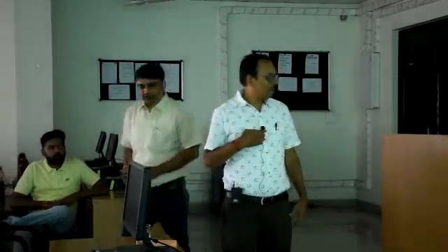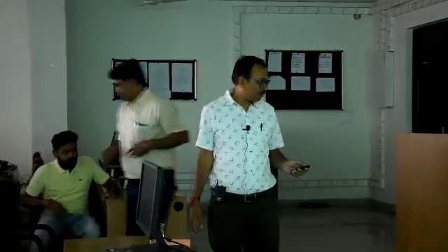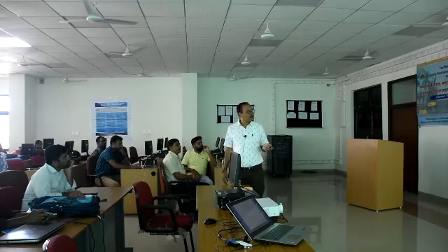Okay, so we can continue. We are discussing the first case. In the first case, this 1 megawatt PV plant is introduced in this network, and it is controlled in volt-var mode. Volt-var means the basic objective is to utilize the facility of your converter, which is used for the PV plant, for some other purpose which helps to stabilize your grid. Either during the night time or when you have less power generation due to the wind flow, that facility is used to stabilize your grid's supply. So this is the reactive power injected by the converter with wind power plant number 1.